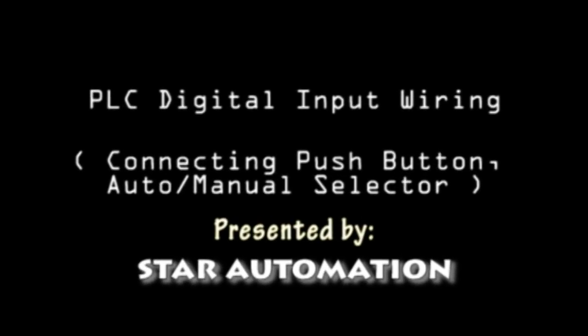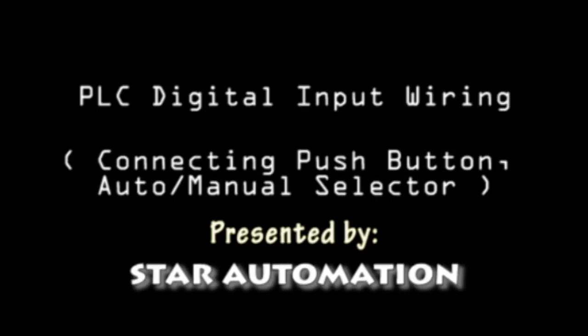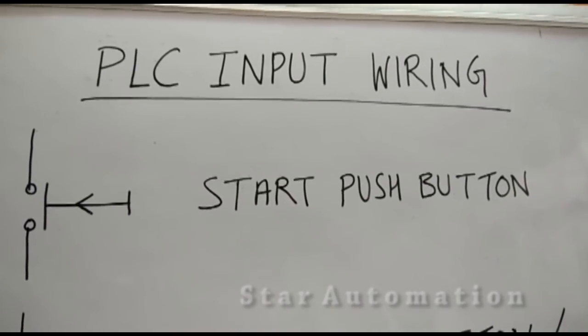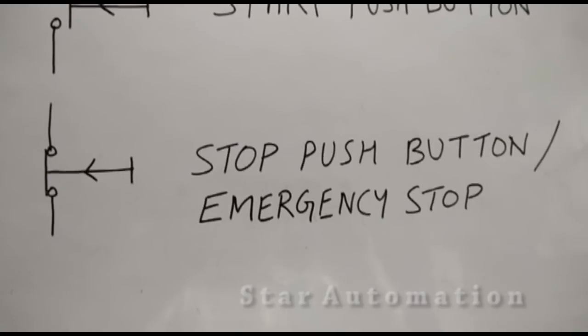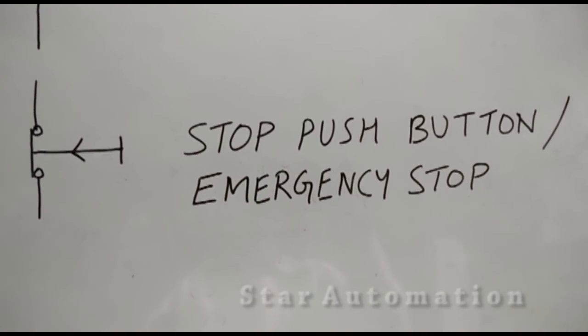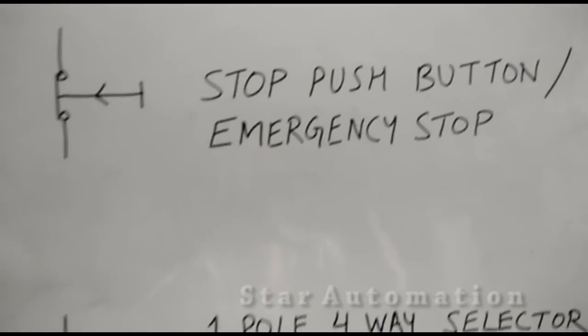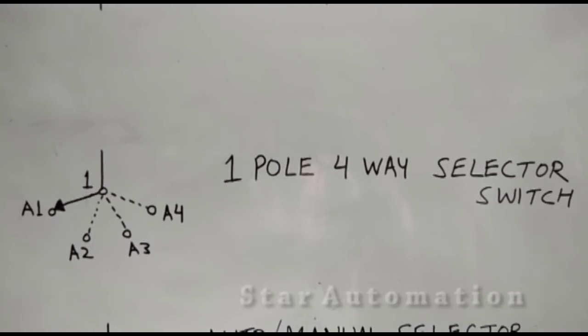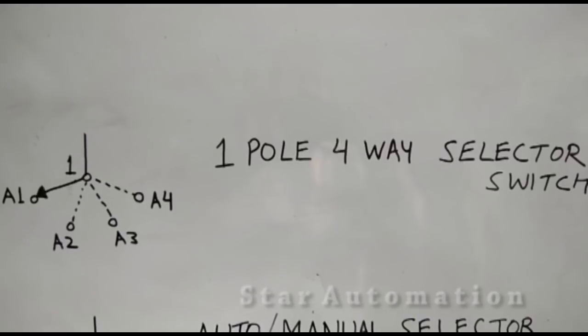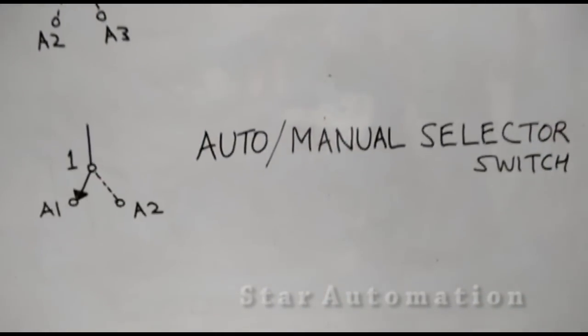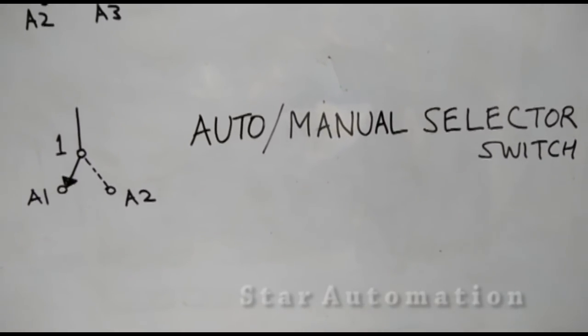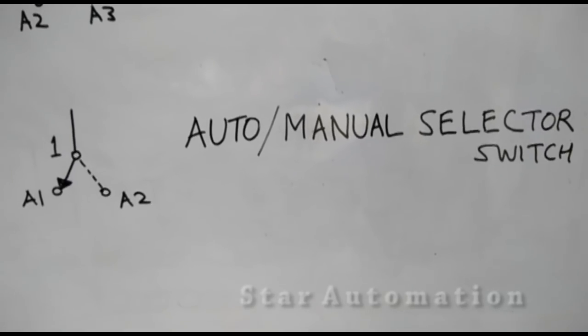PLC digital input wiring: connecting push button, auto/manual selector switch to the PLC input terminals. The start push button is a normally open contact, and the stop/emergency stop push button is a normally closed contact. A one-pole four-way selector switch has one pole and four outgoings: A1, A2, A3, A4. The auto/manual selector switch has one pole and two outputs — one for auto and one for manual.